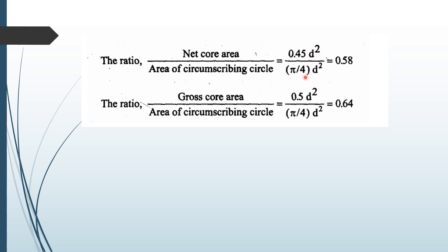The net core area to circumscribing circle area ratio equals 0.45 d² / (π/4 · d²), and the gross core area ratio is 0.5 d² / (π/4 · d²) = 0.64. There is a difference between these two ratios: the net core area ratio is 0.58 and the gross core area ratio is 0.64.